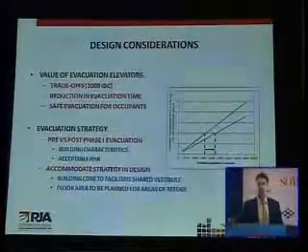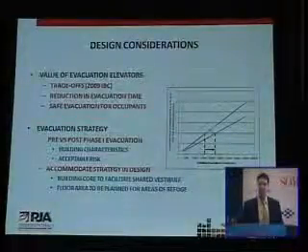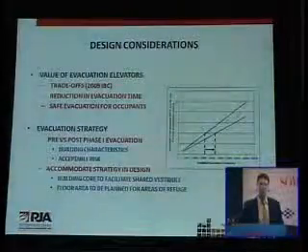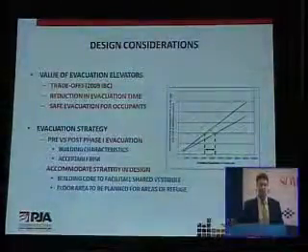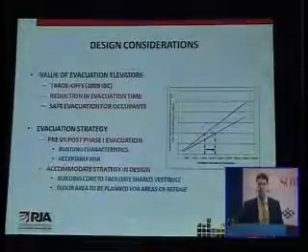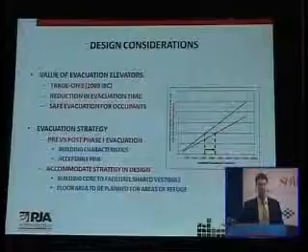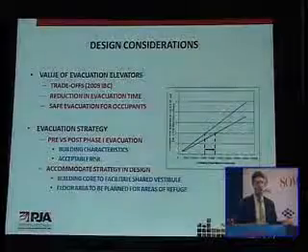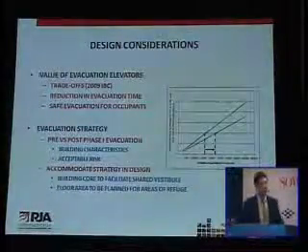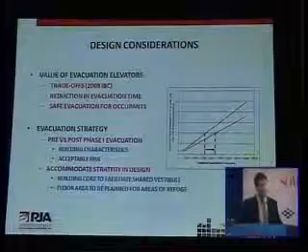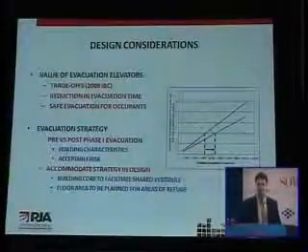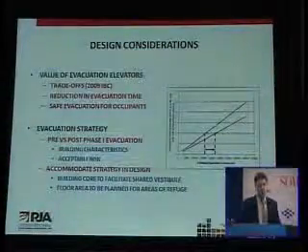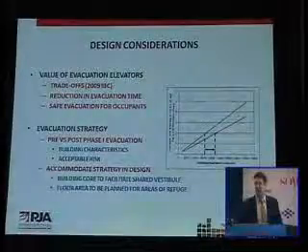It could work for a residential building of about 60 floors or less, where you have a very low occupant load. You could fit potentially an entire floor into a single elevator or 2 elevators. But you need to work with your vertical transportation consultants to make sure that they've set those priorities in advance so that the elevators aren't stopping at multiple floors. You don't get the instances that Jim had mentioned of overloading elevators or occupants not letting the doors shut, those types of things.